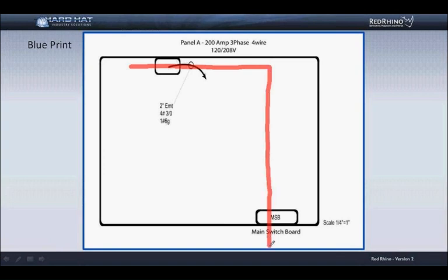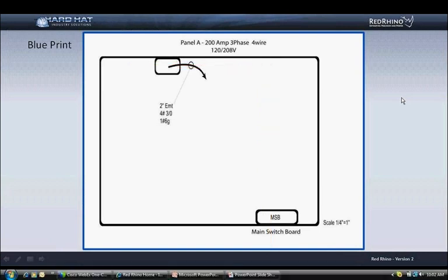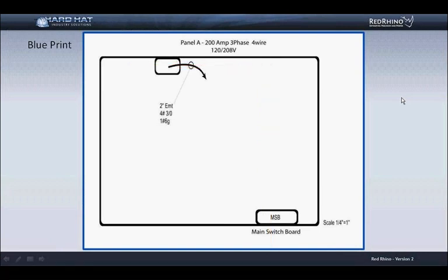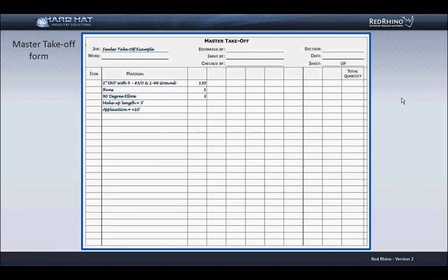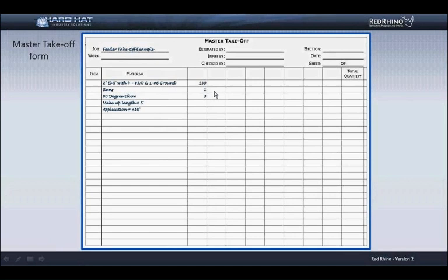Okay, let's assume you have everything set to roll off the feeders and are ready to start. I roll the Scalex over the path of the conduit at a right angle. I'm going to overroll slightly to cover the amount of conduit riser. Since I'm using a virtual Scalex, you cannot see the length that it's measured. In this example, I'm going to say the Scalex shows that this run is 130 feet long. I take this information and write it down on our takeoff sheet. Here's an illustration of how to write the conduit information on the takeoff. 130 feet of 2-inch EMT conduit with 4 number 3/0 copper conductors and 1 number 6 copper ground runs equals 1.